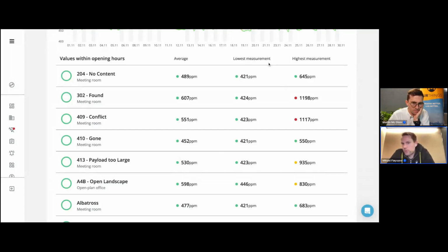It's almost the opposite here, because Airthings has been very air-quality focused, it's been all about low CO2 levels being good, meaning lots of fresh air. But it can also mean you have too much fresh air. So what you'll look for is whether everything is in the green, with no CO2 averages or highest measurements above, say, 600, 700, 800 ppm. If so, that's an indication you're over-ventilating. You don't want very high peaks, at least not frequently, but you also don't want CO2 always low, because that indicates you're blowing way too much fresh air into your building compared to how it's actually being used.